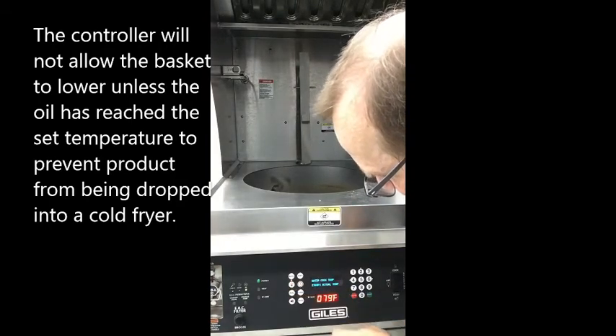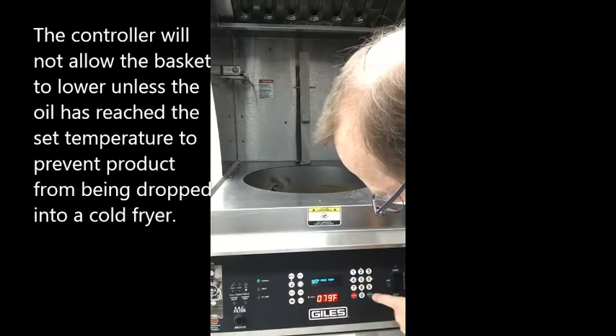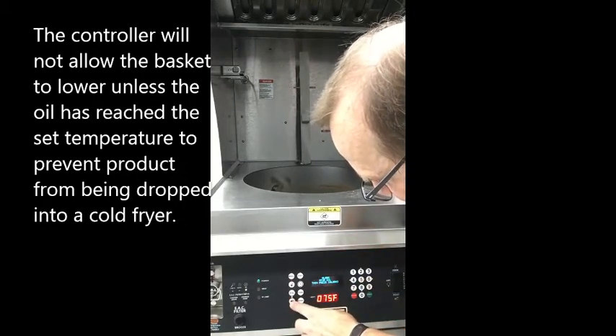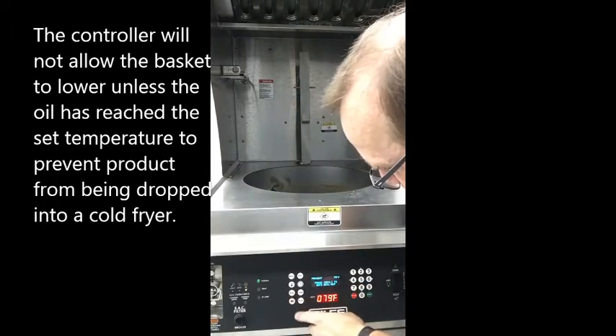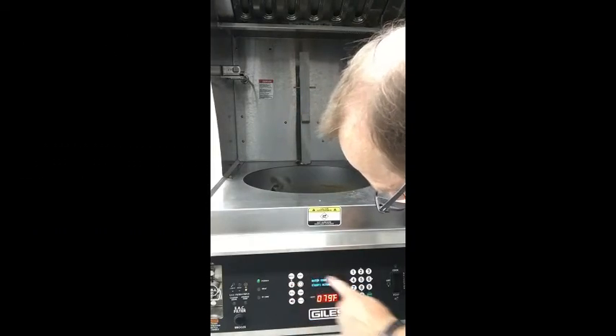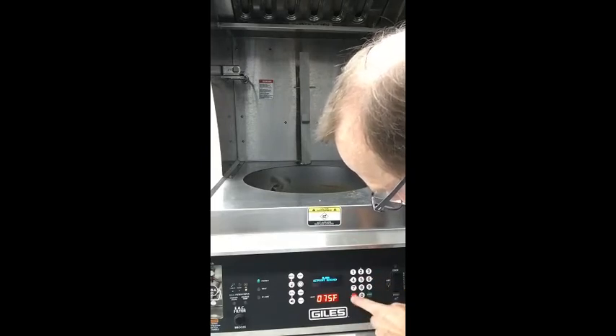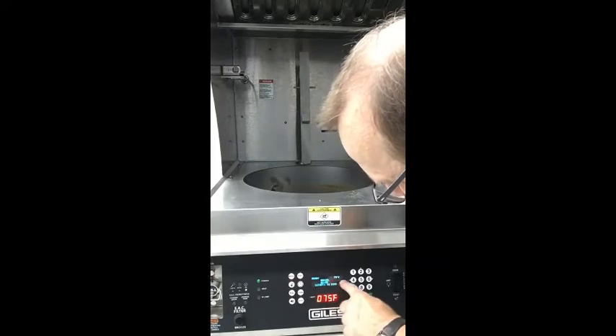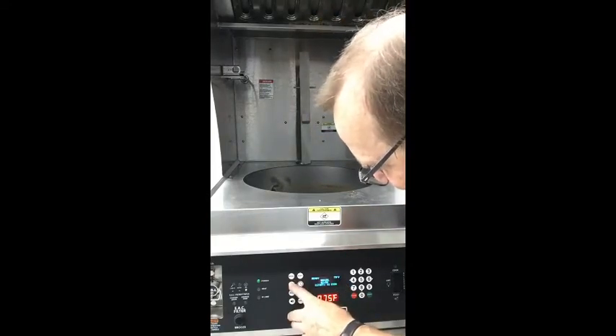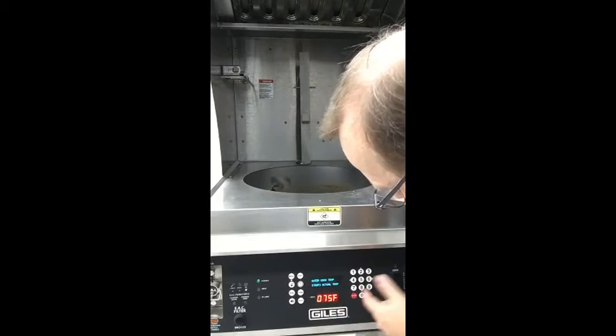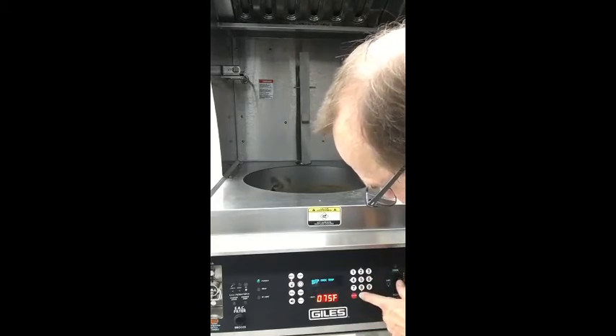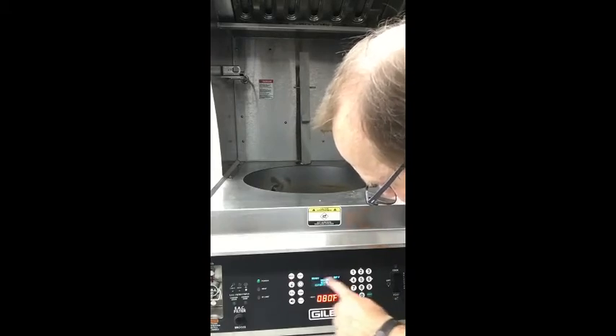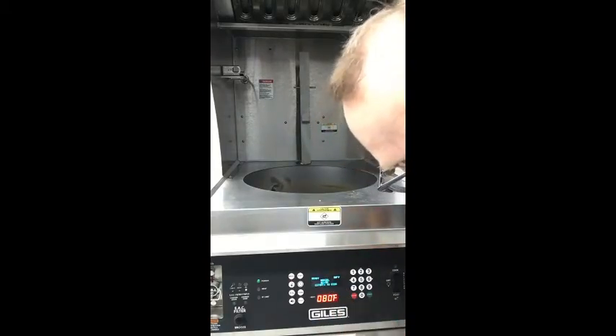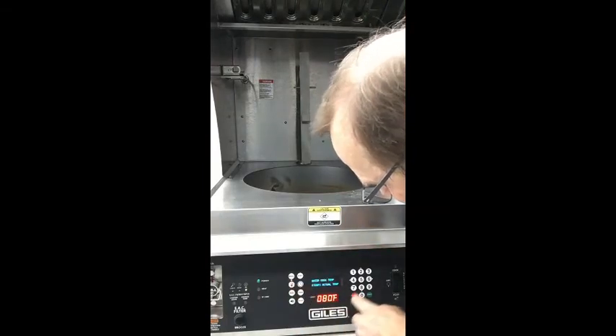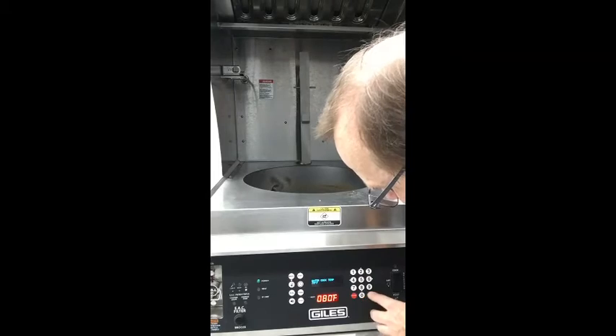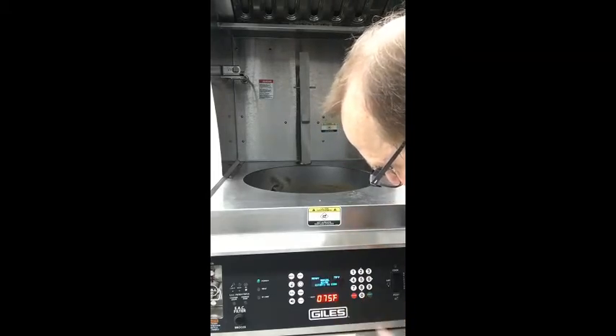We'll set our temperature to 75 and start, okay? And you saw how I did that. All I did was press temperature, and then I put, oops, it's gonna keep on alarming to tell me that it's up to temperature now. But again, you're gonna hit temperature, and just for the sake of it, we'll do 80, and then start. Okay, now that's a manual temperature, and it says it's manual. So let's go back to where we were, temperature, 75, start. Wait for it, see if it's gonna alarm. I don't think it's going to.